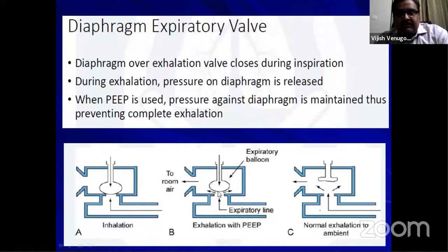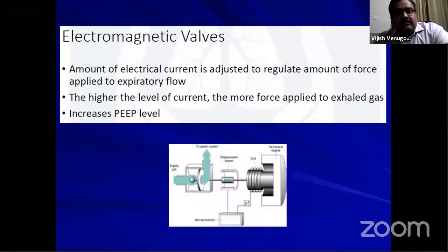Whereas the amount of PEEP that you give to this diaphragm expiratory valve, there will be a restriction and PEEP will be developed. The other third one is the electromagnetic valves. Here, an amount of electric current is adjusted to regulate the amount of force applied to the expiratory flow. So the higher the level of the current, the more the force applied and the more the PEEP level. And this is the one that is now commonly available in our ICU ventilators.